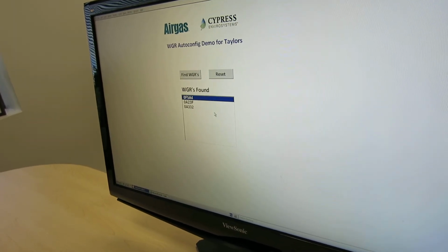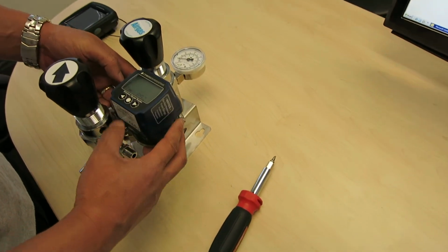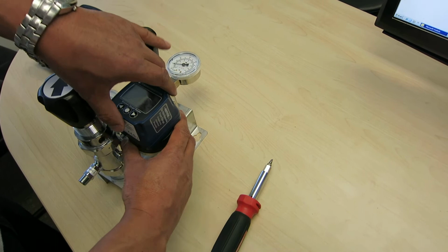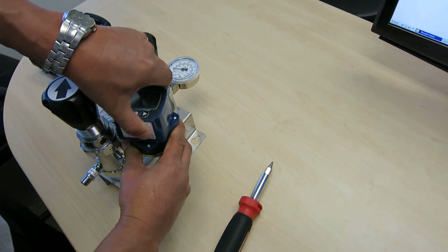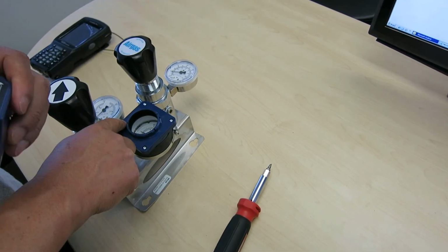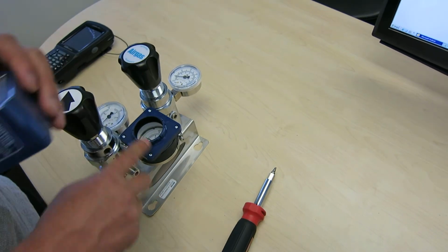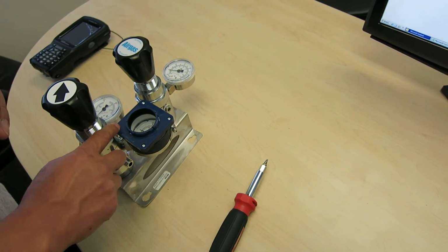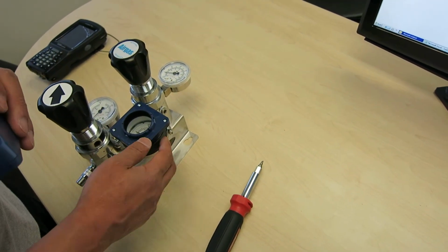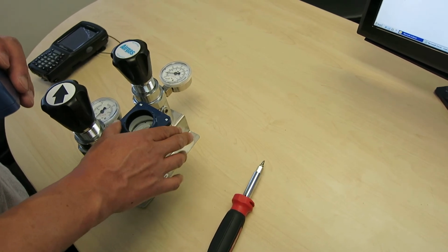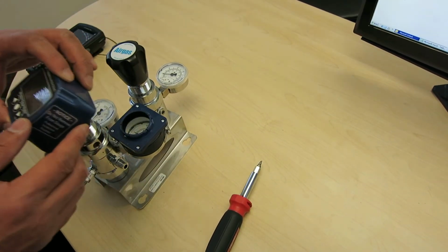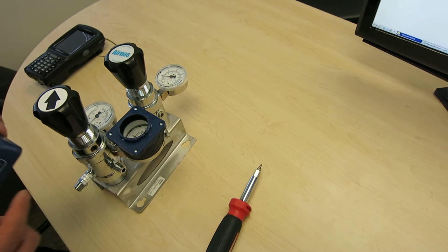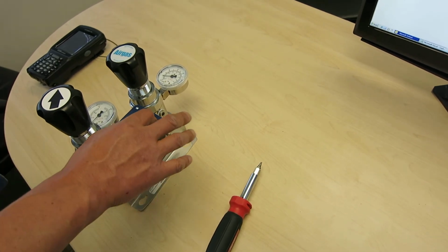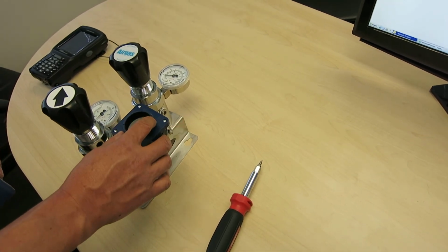Okay, now I come back to the WGR, and I'd just put it back into normal mode, and it's configured. Now I can just remove the WGR, and this unit can ship, the regulator can ship with this adapter on. Now actually, we found that our shim needs to be adapted a little bit so it's on more tightly - that's something we're going to adapt for this particular gauge. But the idea now is that this adapter is fixed onto the regulator.